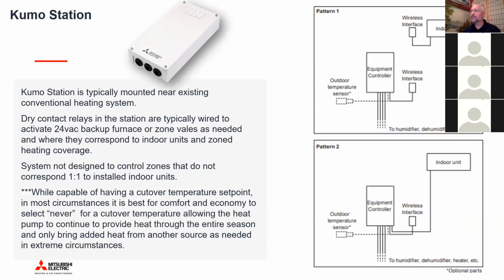It can be connected directly to an indoor unit, and the prime example of pattern 2 where it's directly connected to an indoor unit using the CN105 port is where you're tying it into a furnace, and you're controlling a furnace, and maybe an air handler, and so maybe you have that next to a furnace and they're kind of going through one another for backup. There's a bunch of other strategies, but that's pretty common. I don't think that's going to be common with integrated controls, but that's a strategy that is normally the case if somebody wants Kumo, but they're tying into a piece of equipment that's directly next to them.